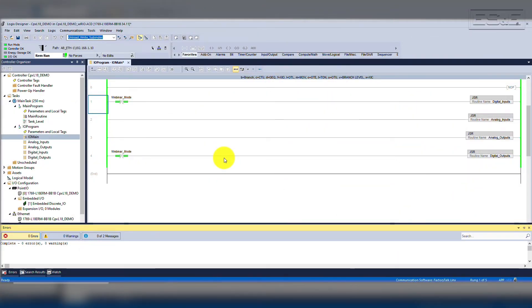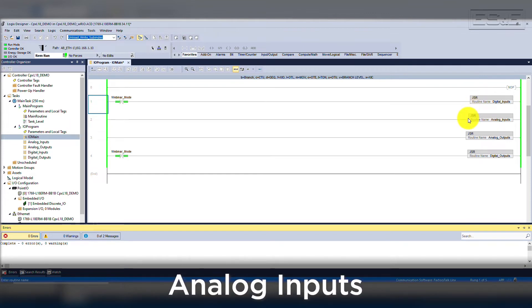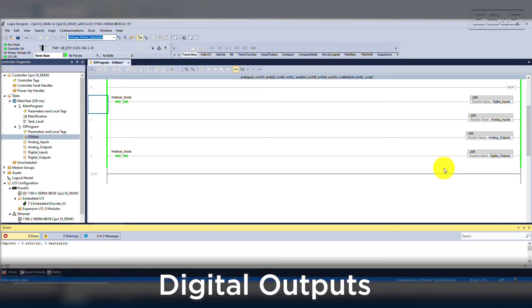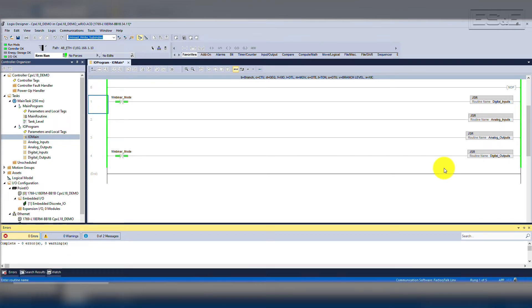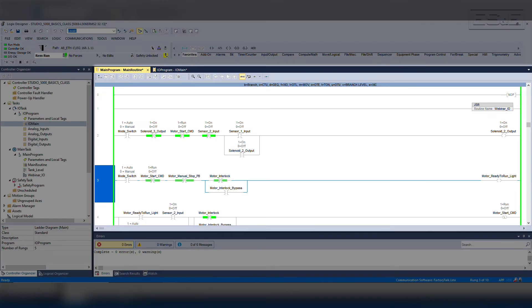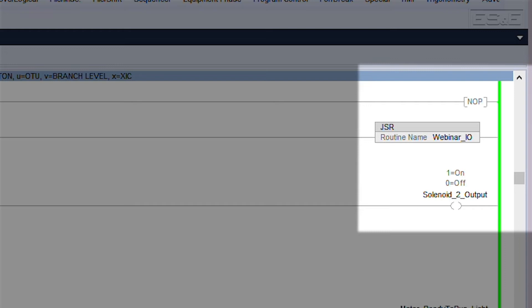The scan sequence will scan digital inputs first, then analog inputs, analog outputs, and digital outputs last. I have created an extra tag that prevents the JSR from executing the code for the purpose of webinars and training. We will select the tag and press Ctrl-T, which will toggle the tag since it is not being overwritten by any other code. The majority of our code will be done in the main routine. Inside the main routine, I have a JSR jumping to the function block routine called Webinar I/O.